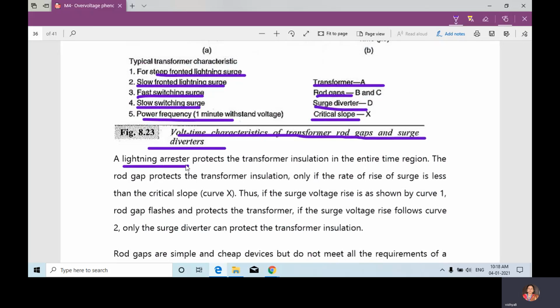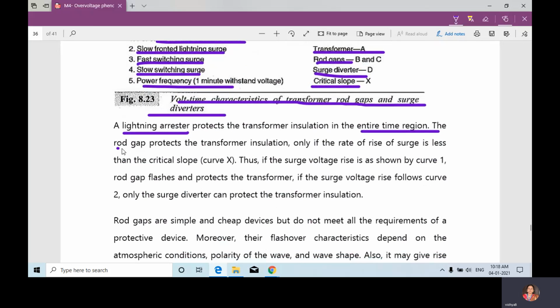A rod gap is also used to protect the transformer insulation, and a lightning arrestor is also used to protect the transformer insulation, but the lightning arrestor protects the transformer insulation in the entire region. Okay, this is the difference. The lightning arrestor will protect the entire region, and what does the rod gap protect?